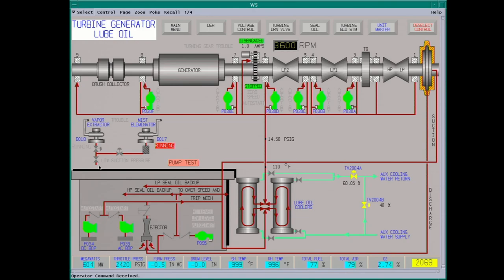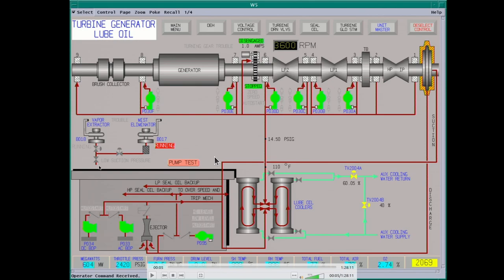Some of the stuff is really hard to explain going through so fast. The first thing we'll see is the turbine lube oil tank. The tank has the DC bearing oil pump on top, the AC bearing oil pump, the ejectors inside, and we also have the seal oil pump. In normal operation you have your main lube oil pump on the end of the turbine shaft. High-pressure oil comes down to the lube oil tank. There's an ejector that takes high-pressure, low-flow oil and converts it to low-pressure, high-flow. Part of this oil is used to feed the suction to the pump.